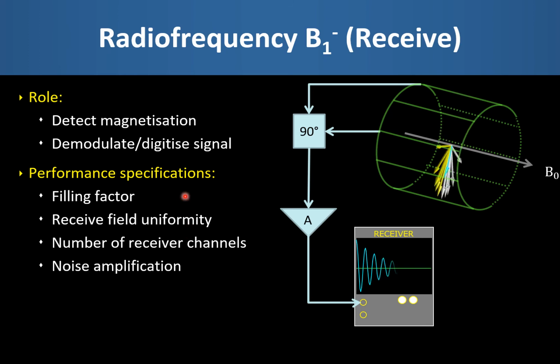The performance specification of the receiver coils are firstly that they should have a very good filling factor. This means that the coil needs to fit the anatomy of interest as closely as possible to maximize the signal and therefore the signal to noise ratio. Ideally, the received field should be uniform, but the trend these days is to have multi-element array coils that are very good at detecting the signal very close to the elements, but not quite so sensitive to signals deeper in the body. However, there are several other advantages from having dense arrays of smaller sized coils.